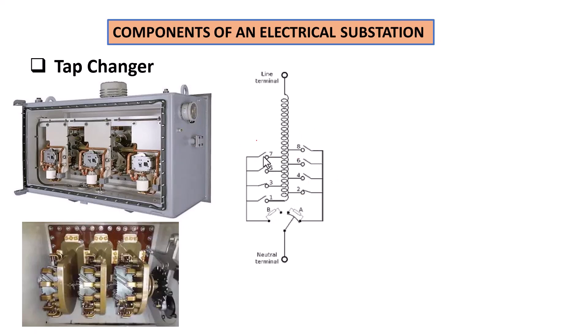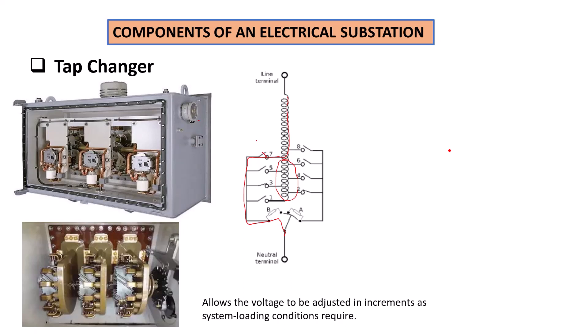By changing the position of the tapping, we will actually be changing the voltage ratio, and that will maintain regulation on the secondary. As you can see here, if we close this switch on tapping number seven, the current will flow down through the coil and through to the neutral connection. This means we're not going to make use of all sections of the coil, and by not using that section, it will alter and change the turns ratio between the primary and the secondary — and once that changes, it will result in changing the voltage ratio as well. In short, a tap changer basically allows the voltage to be adjusted in increments as system loading conditions require.